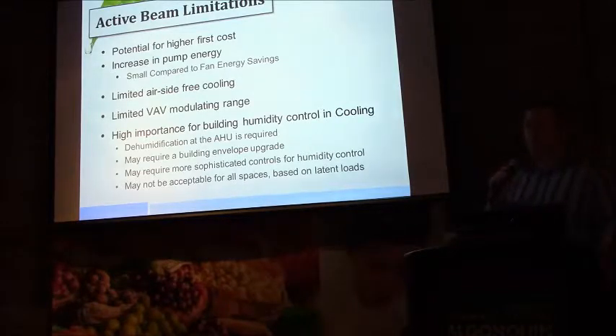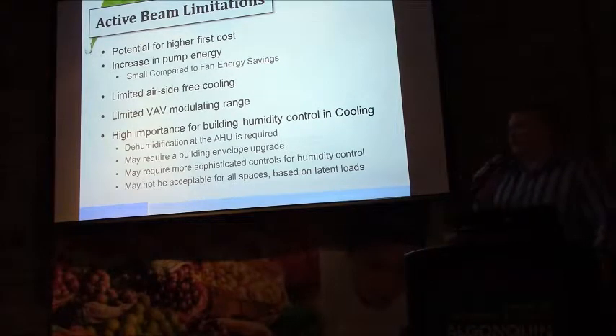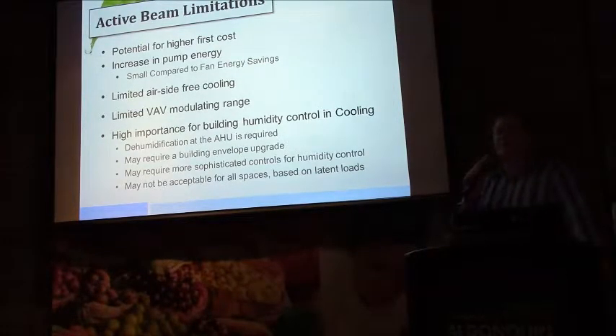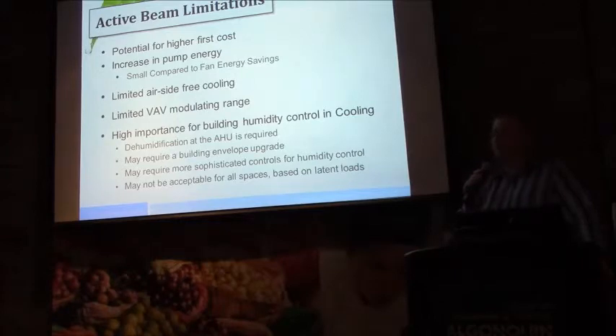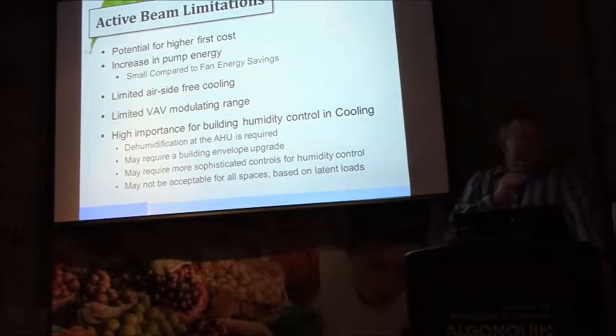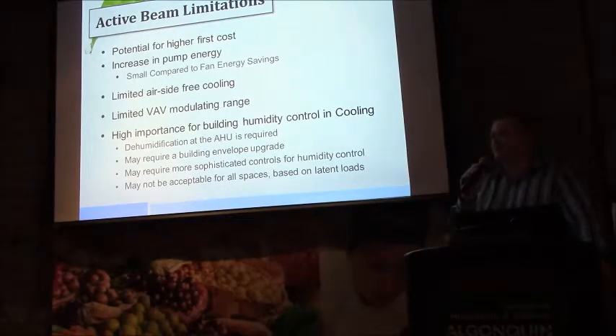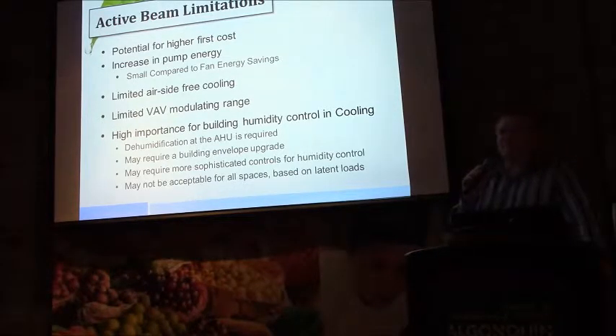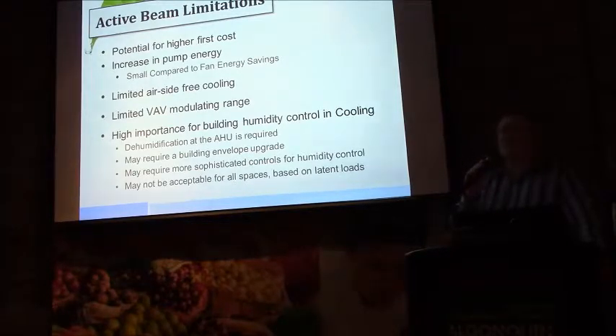Humidity control is paramount. It's not an issue if we understand the loads in the space and the construction of the envelope. It is a talking point relative to the design team to ensure that the envelope can support low total air flows into the space. In the beginning, for construction that could be suspect, a discussion relative to a blower door test for the space to ensure that the building is properly sealed and that the infiltration loads are under control could be a talking point. There's a cost to that, obviously.